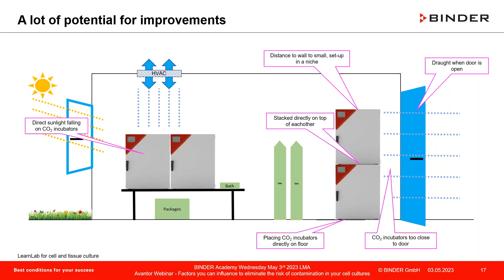Also very important, always consider the right distance of CO2 incubators from the wall. That is very much like at home when you have a closet. Please don't push it directly against the wall because there you have no or too low air circulation. You might have humidity, condensation developing there, and in turn, over time, molds coming there. And that's something we do not need. So always take care for the proper distance from the wall and also between them, not next to each other. Anything where you can't put a finger in between is wrong. At least 50 millimeters. That is the least distance between two of them standing next to each other.